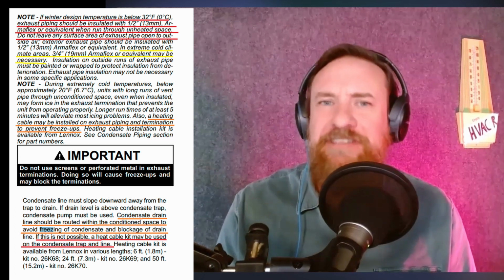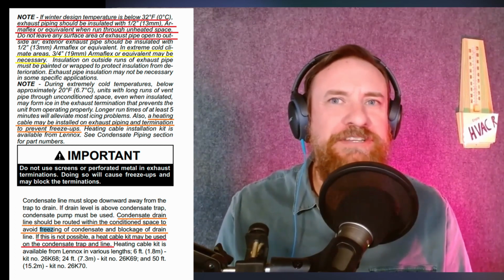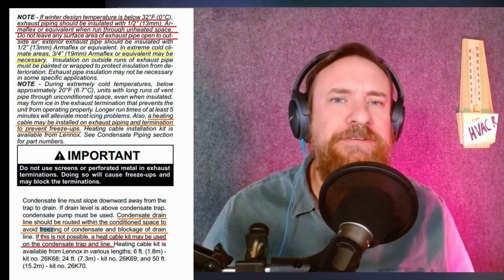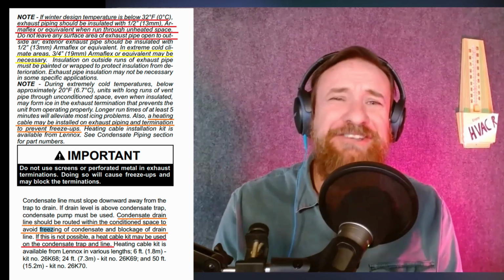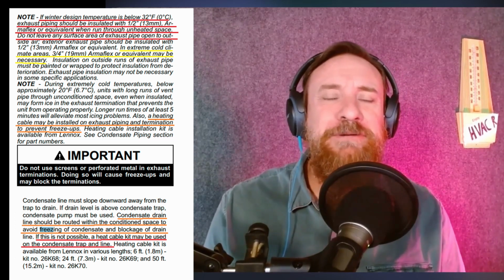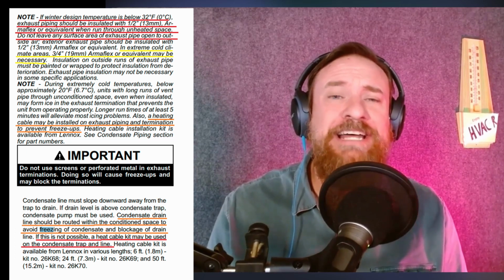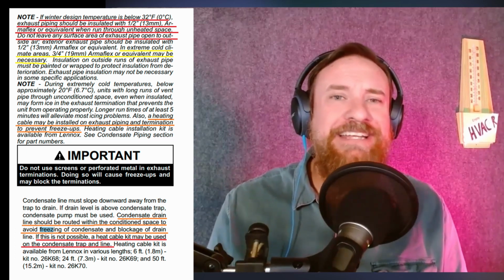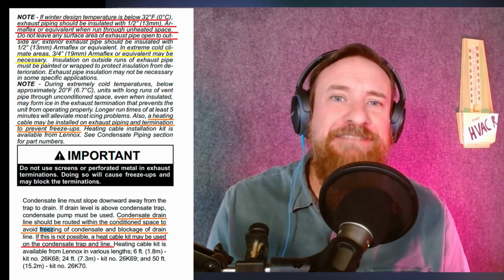How about if we read the installation manual and maybe follow some of those rules? It would solve a lot of them, not all the problems, but it would solve an awful lot of those problems. So again, the installation manual is so important. It actually says it prefers that drain line to be run in conditioned space. Really, a 90% furnace should never have its drain line run outside anyways.